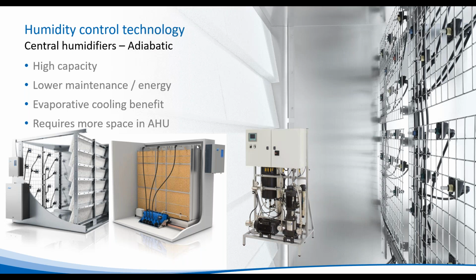But if you need better than that, then you would use a system that uses both spray technology and evaporative technology. Here you can see a dual technology system where you've got a nozzle array spread across the whole cross section of the air handling unit. And when we get a demand signal, one or a number of these nozzles will spray water in a very fine aerosol.